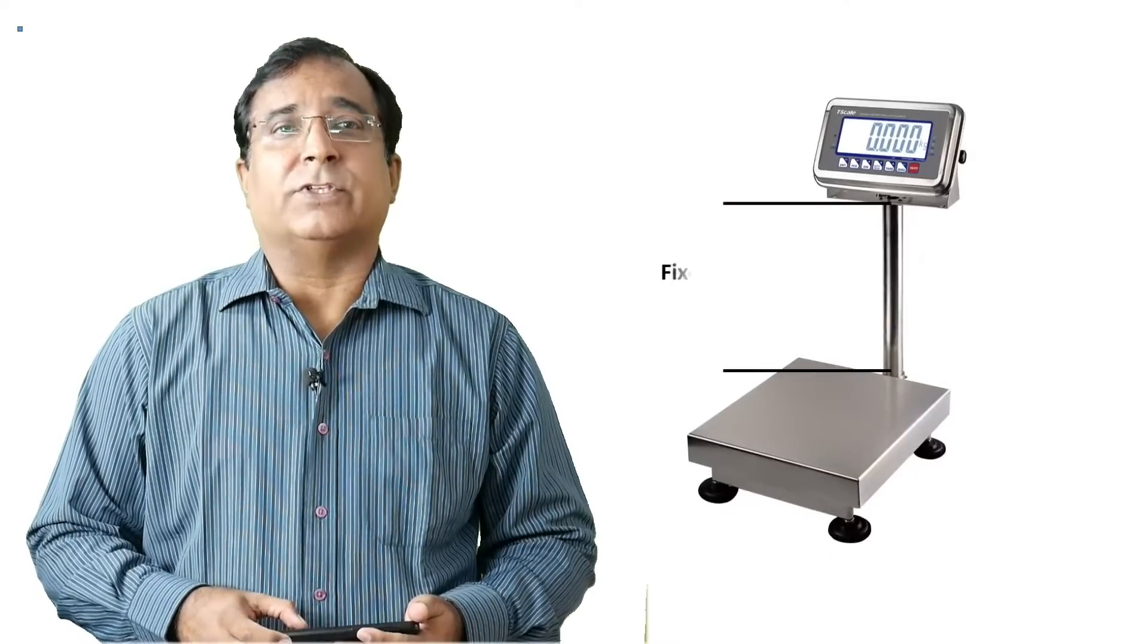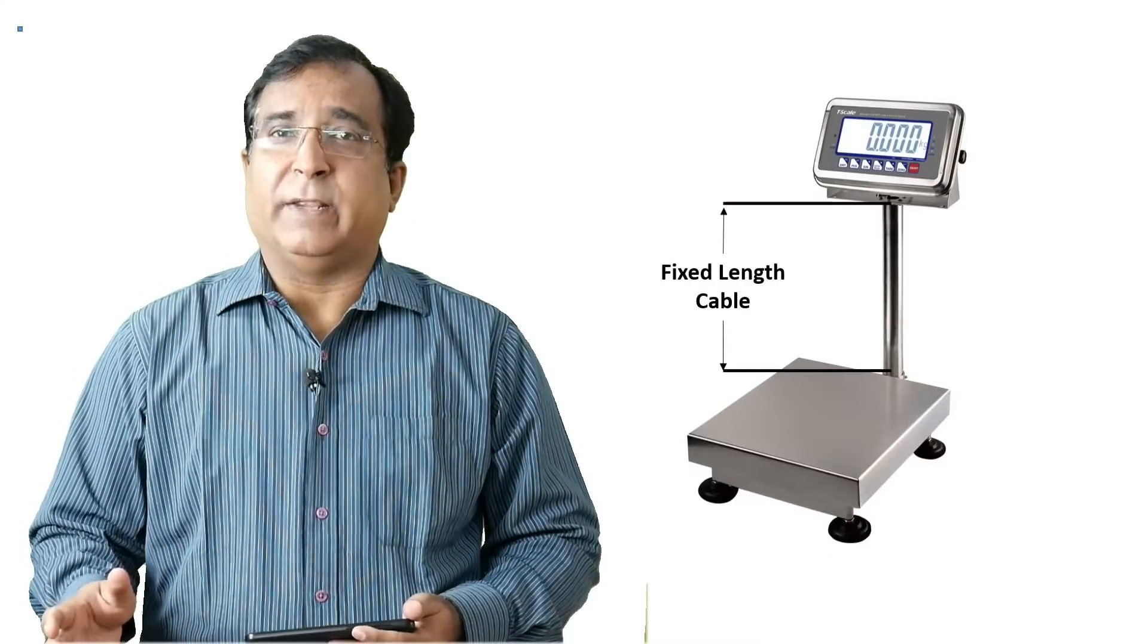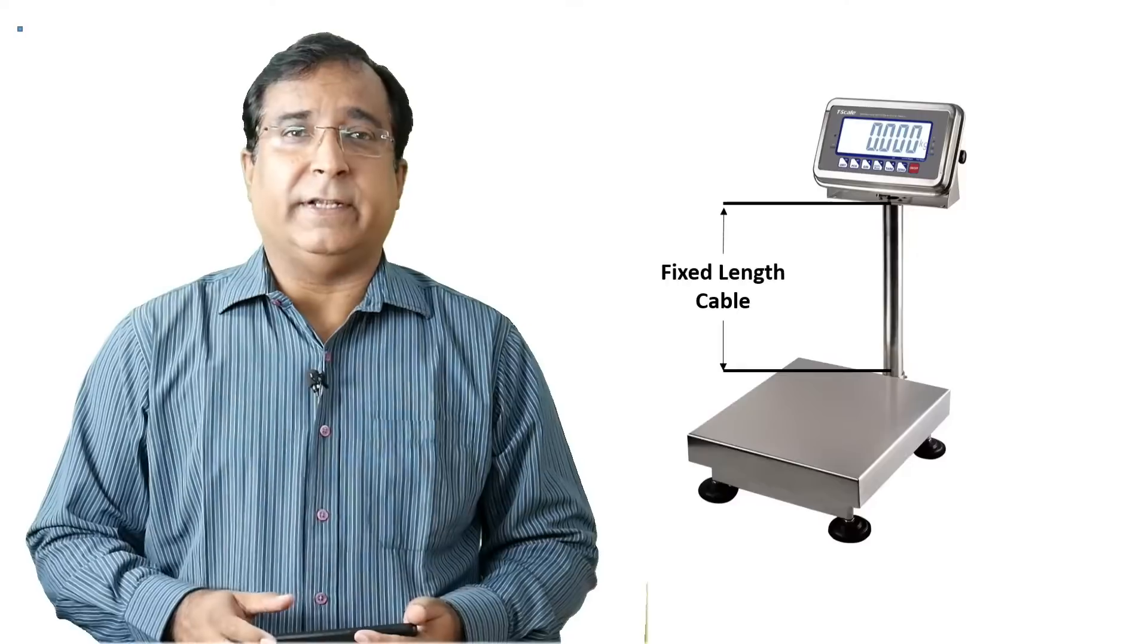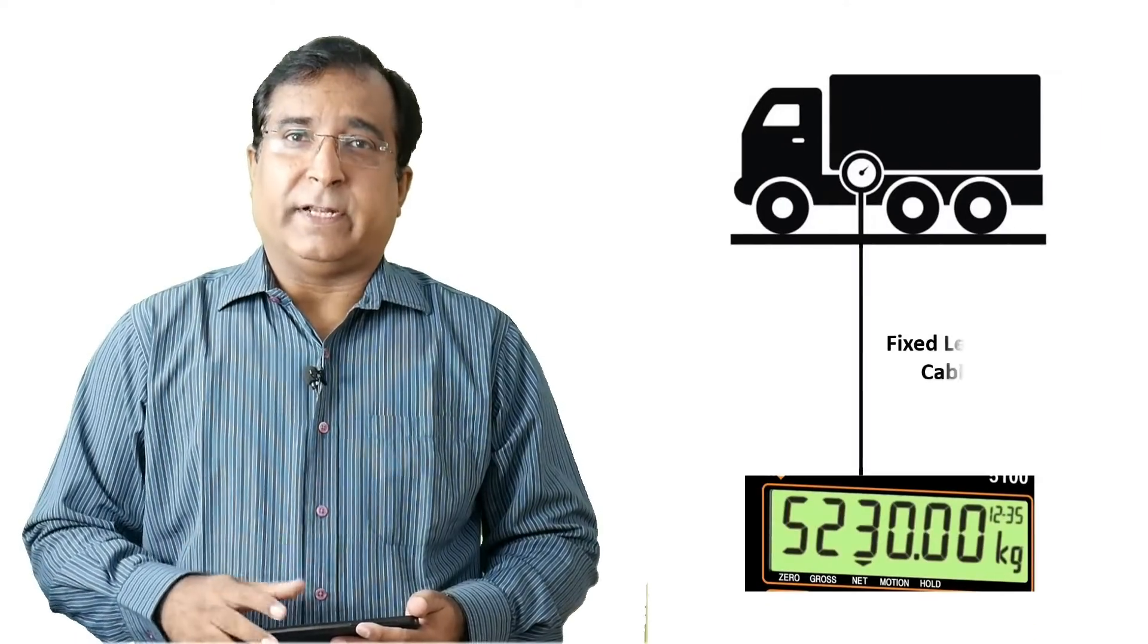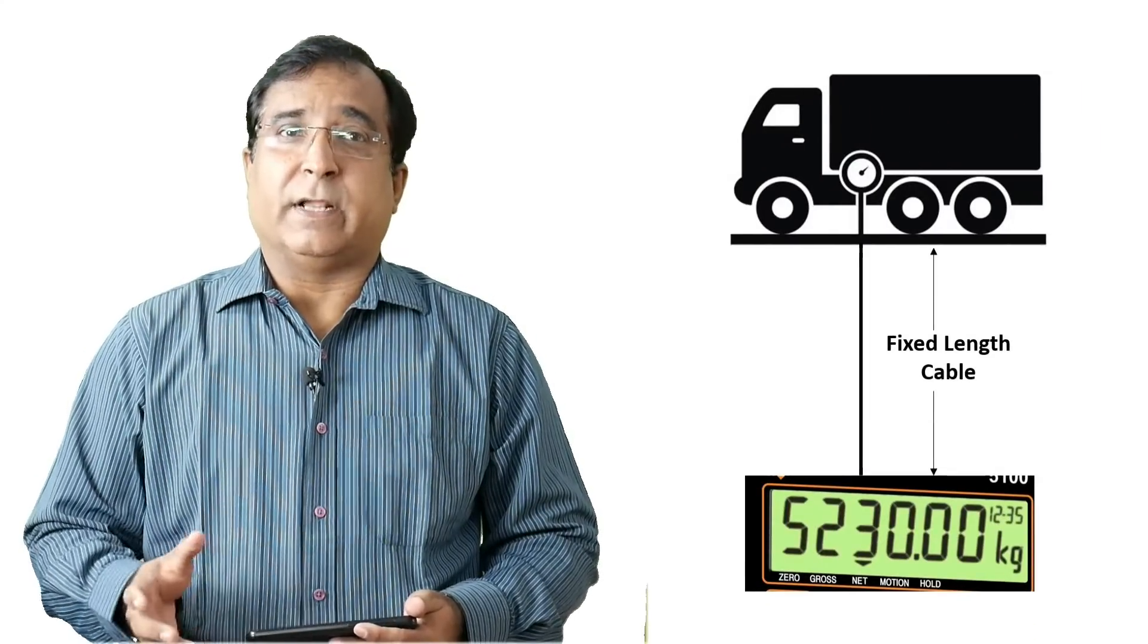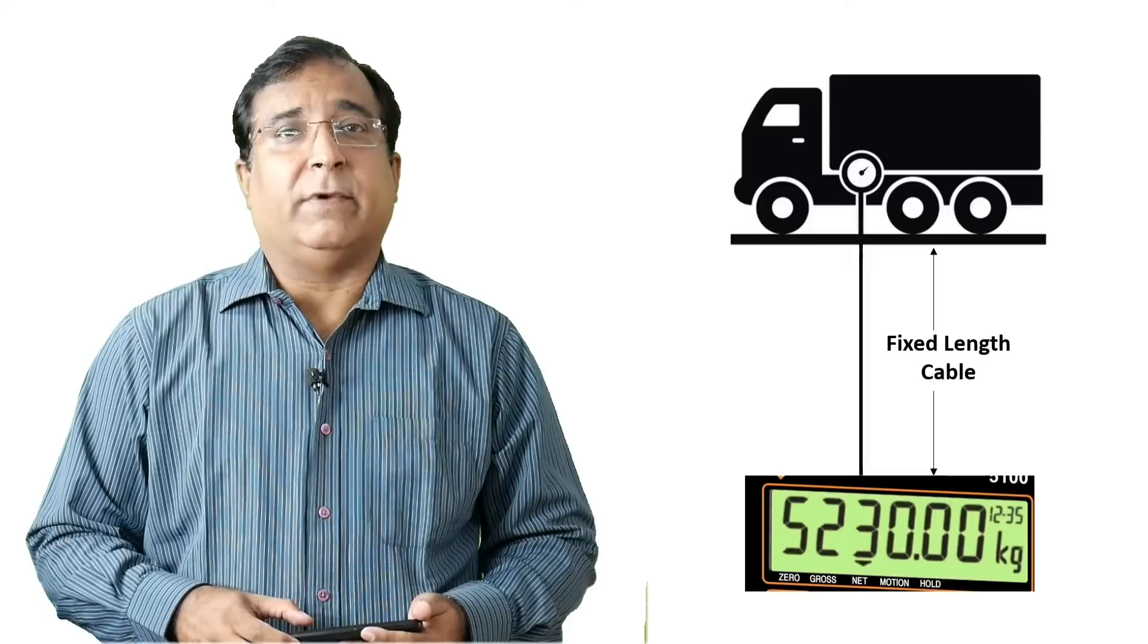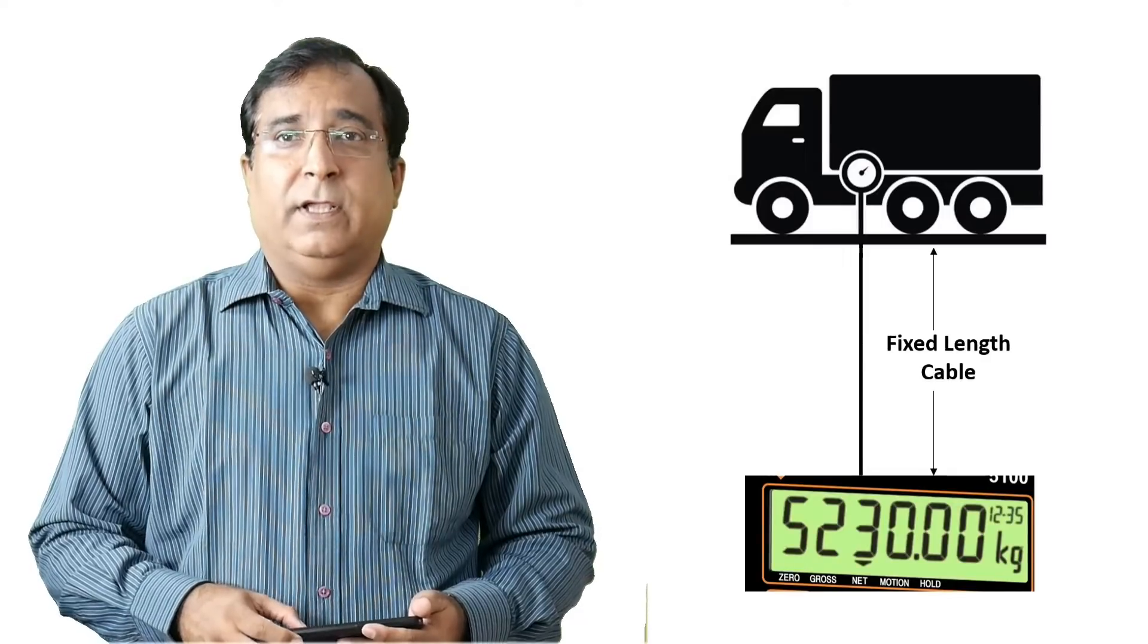4 wire load cells are mostly used for local weighing machines or for static weighments where the weighing platform is located near the indicator. This also reduces the cost of a load cell. And these weighing scales are factory calibrated and hence it is recommended that you never cut the cable of 4 wire load cell as they are factory calibrated for a fixed length. There is no cable length compensation in this type of weighing scales.